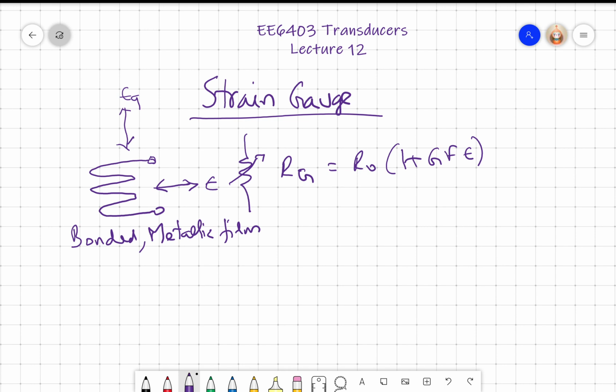Ideally, a strain gauge is not expected to respond to strain in the quadrature axis, but practical strain gauges will have a small cross axis sensitivity. So if in the main axis the sensitivity is 100, then cross axis may be 1 or 0.5, like that. Normally the cross axis sensitivity is given in terms of the main axis sensitivity, saying that cross axis sensitivity is 1% of the main axis sensitivity. So if you do not want a strain gauge which has a cross axis sensitivity, you must look at this particular specification when you choose, right?